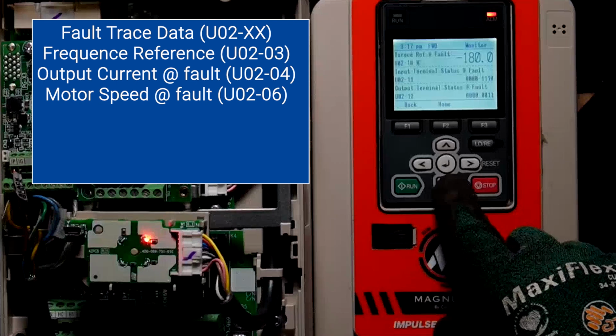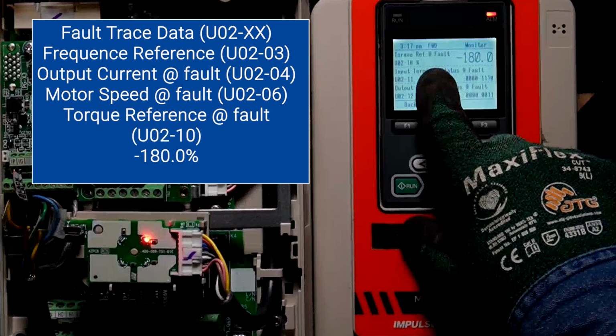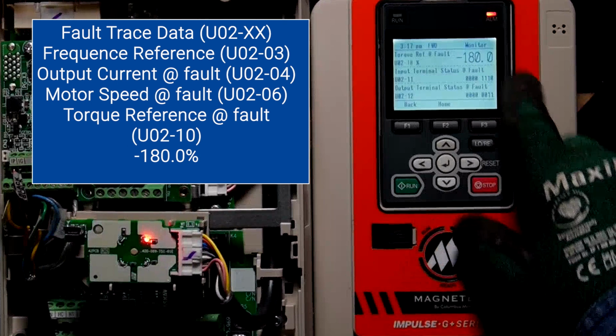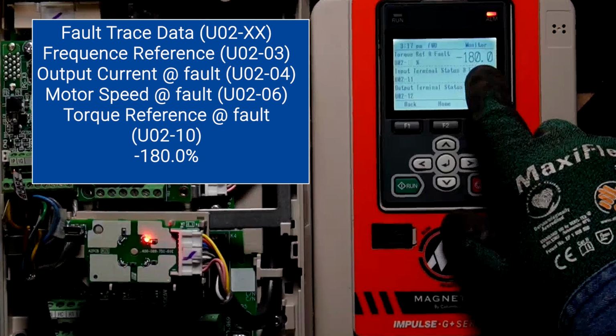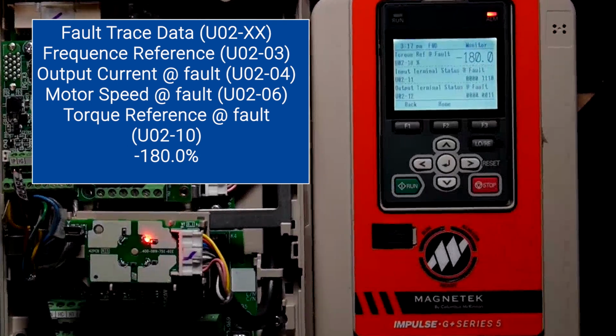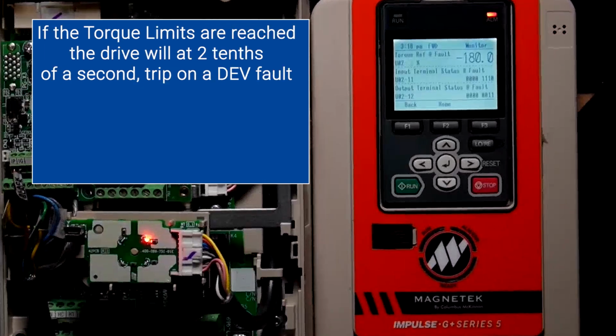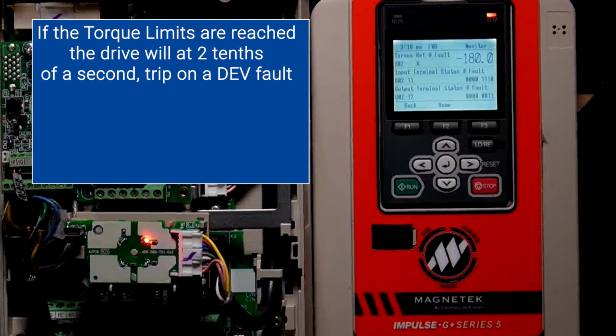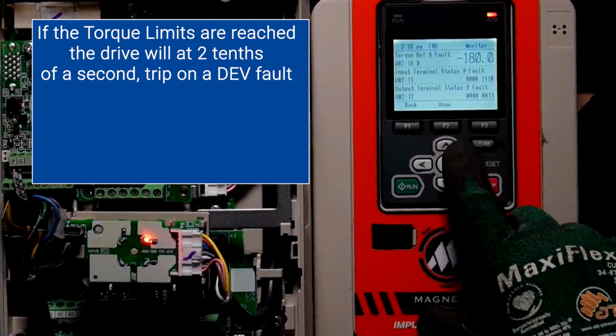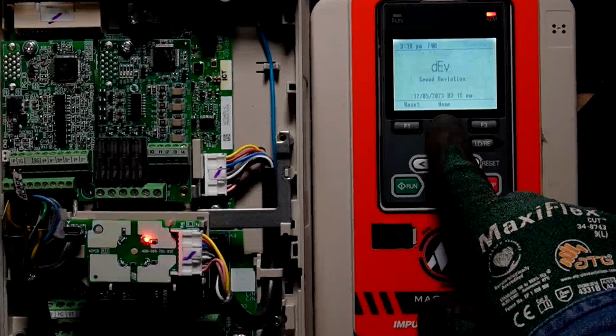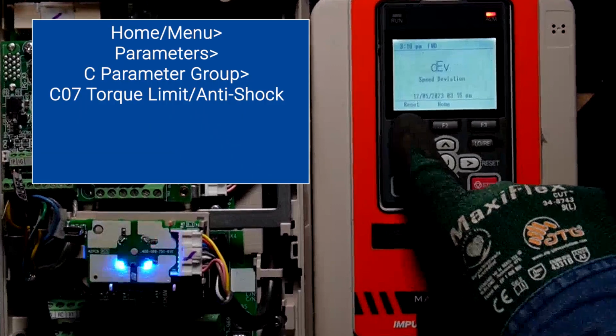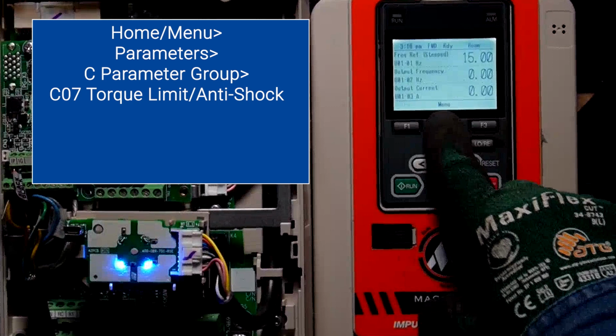This is the important one, torque reference at fault. It says minus 180% of motor torque. Now, when you reach what's called a torque limit, the drive will, after 0.2 of a second, trip out on a DEV fault. So what we're going to do, we're going to go into the home, and I'll reset the fault. We're going to go into the menu.